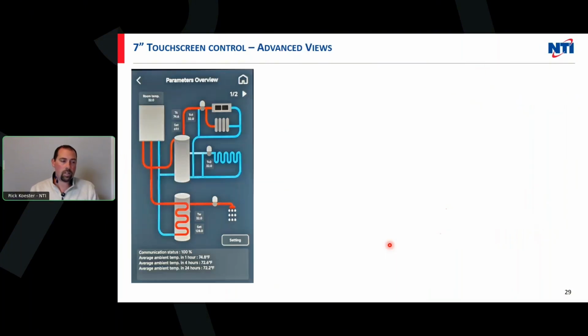If we click on that, you're going to see something that looks like this. I love this. The contractor feedback so far has been great. We've had a couple of classes already, and they love that they can physically see the hydronic system now, as well as, you'll see in a second, the refrigeration cycle. Here you're seeing a hydro box. This is on here regardless of having a control box or a hydro box, but it's a basic illustration of a hydronic system. If you do not have a certain sensor hooked up, or a circuit that's on this diagram, you'll notice that the temperature reverts to 32 degrees.